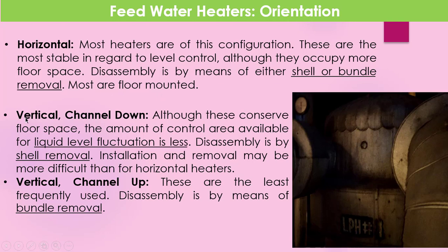And for the vertical feed water heaters, there are two types, channel down and channel up. These vertical feed water heaters conserve floor space. The amount of control area available for liquid level fluctuation is less, and disassembly is by shell removal. Installation and removal may be more difficult than for horizontal heaters.